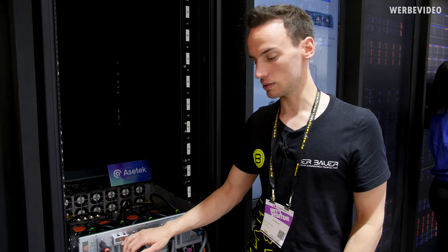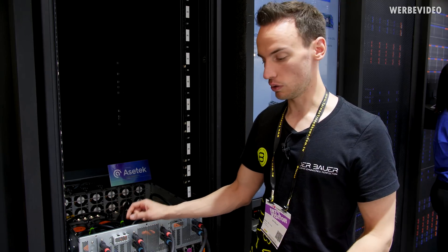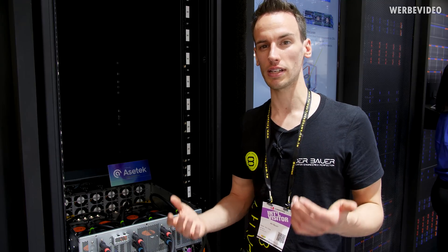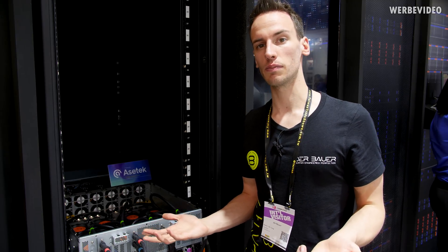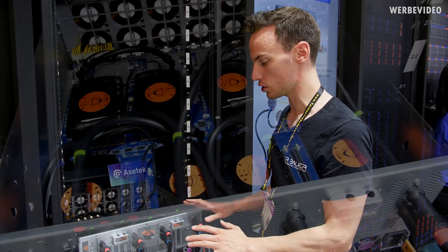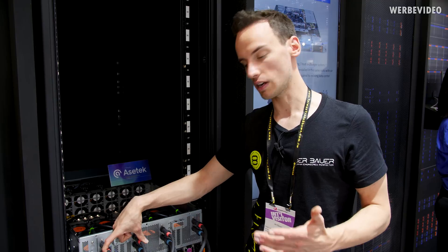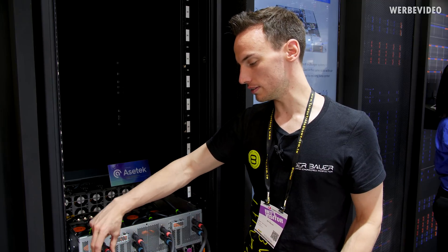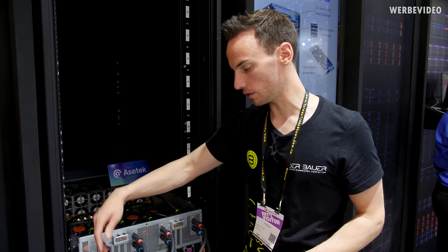Moving to the liquid cooling solution, what I find really interesting is that we have eight cooling blocks from Asetek, and each one includes an individual pump. Typically with liquid cooling you think of one big loop with just one pump providing flow, but in this solution we have eight pumps in total. You can see four connections here — the red marking the hot side, the output of hot water, and blue for the intake. Two V100s are connected to each other over two blocks.